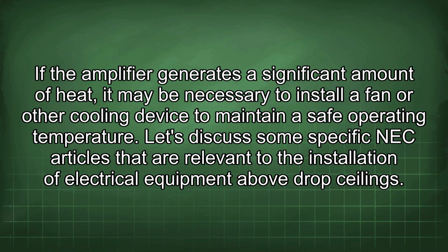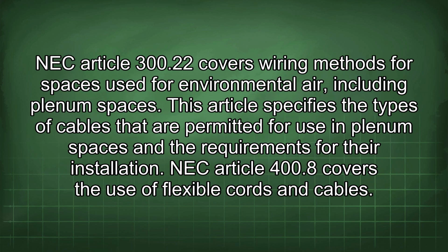Let's discuss some specific NEC articles that are relevant to the installation of electrical equipment above drop ceilings. NEC Article 300.22 covers wiring methods for spaces used for environmental air, including plenum spaces. This article specifies the types of cables that are permitted for use in plenum spaces and the requirements for their installation. NEC Article 400.8 covers the use of flexible cords and cables.